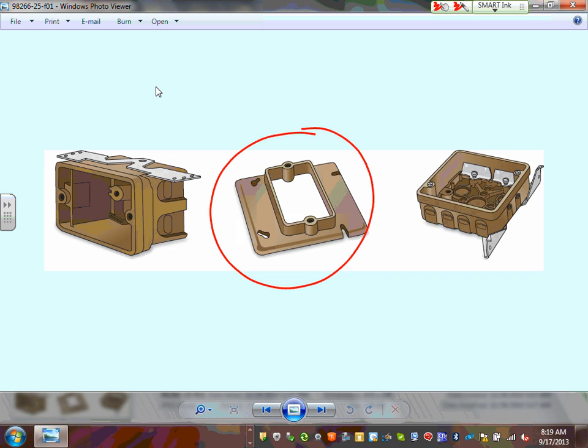Unlike power, why do you think we have a box every time we terminate a switch or receptacle? Two reasons. Number one, shock hazard, because you don't want people around the electrical to shock themselves. And fire hazard, if there is an arc and spark, you want it contained in the box. Now for phone, data, and signals, there is no arc and spark, no fire initiated from these devices. So they're shock free and fire free.